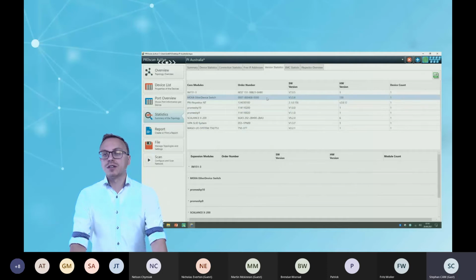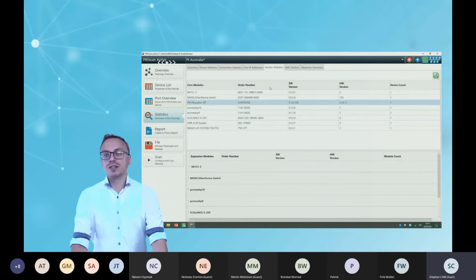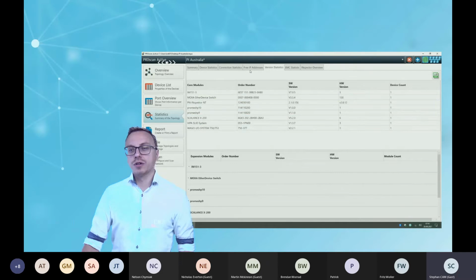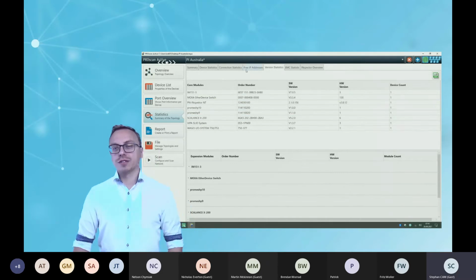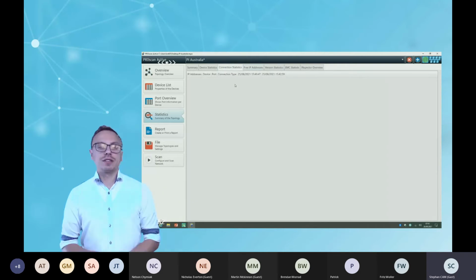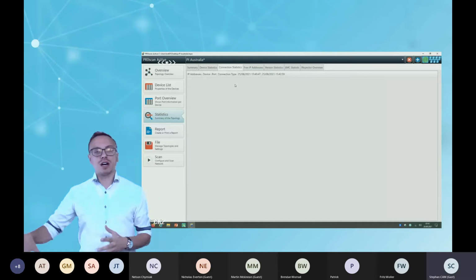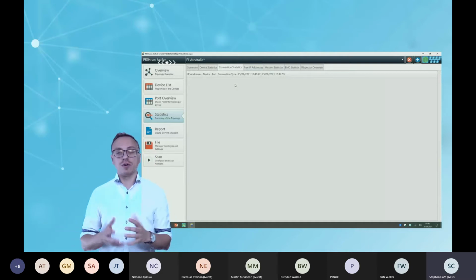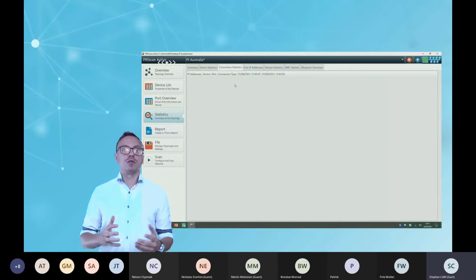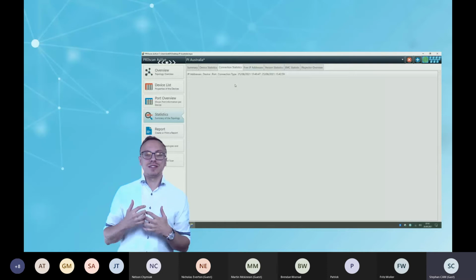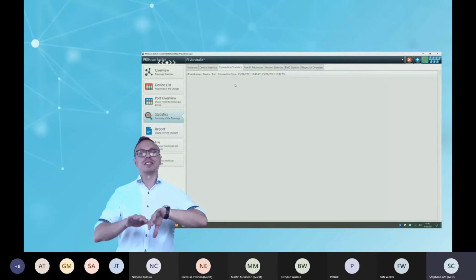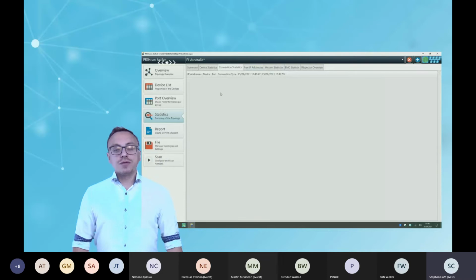You can scan it automatically, and the software will show you in red coloring if you have older firmware versions on your devices or differences. So what else? Connection statistic. As I said, a lot of devices will discard frames if you have a lot of net load, so the device is overloaded, or if you have error frames. In this situation, the device will discard frames. Because of these discarded frames, you don't get the diagnostic information. As I said, PROFINET doesn't have a network diagnostic.